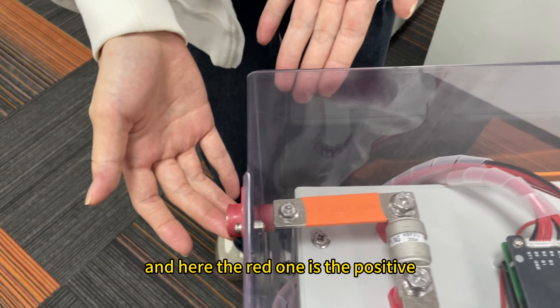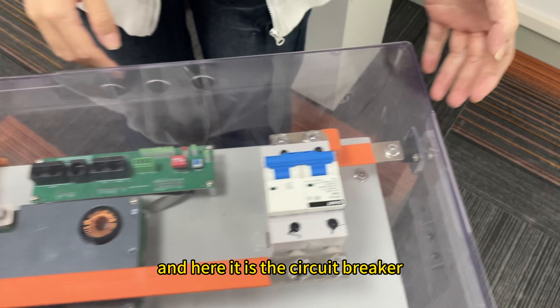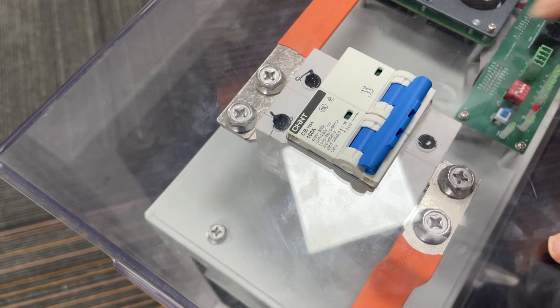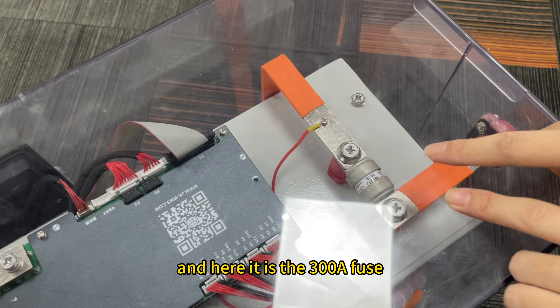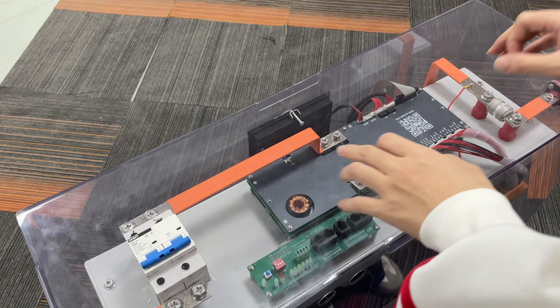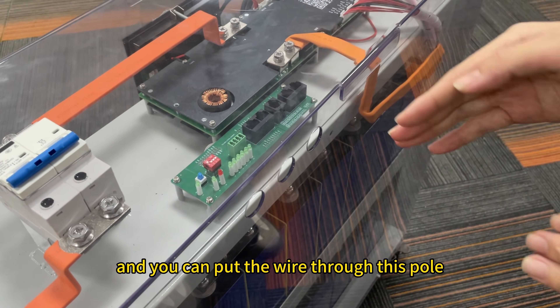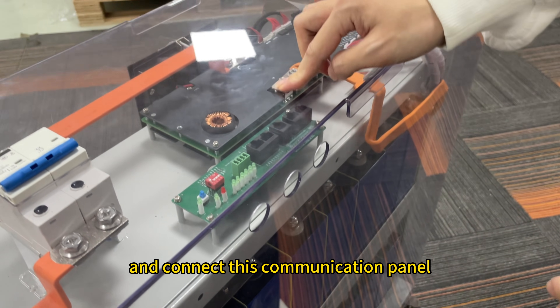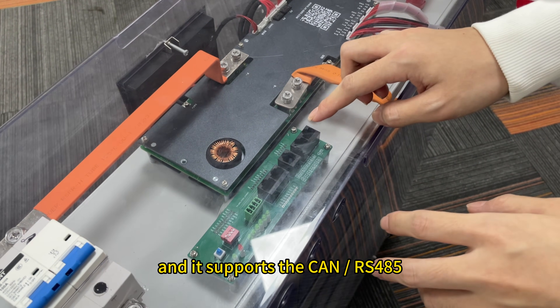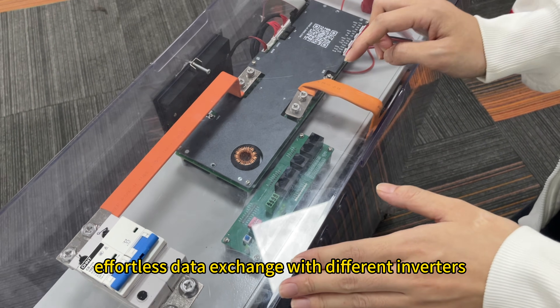Now I will introduce the details of this battery pack. The red terminal is the positive and the black one is the negative. Here is the circuit breaker at 100 amperes, and here is the 300 ampere fuse — they serve as double insurance. Here is the communication port with three ports, and you can put the wires through to connect the communication panel. It supports CAN and RS485 bus communication, allowing seamless data exchange with different inverters.